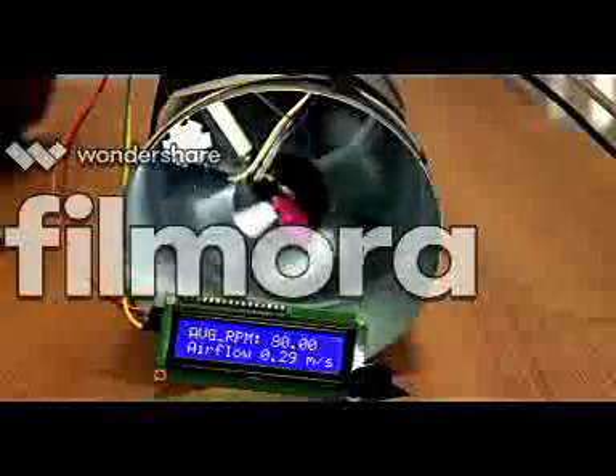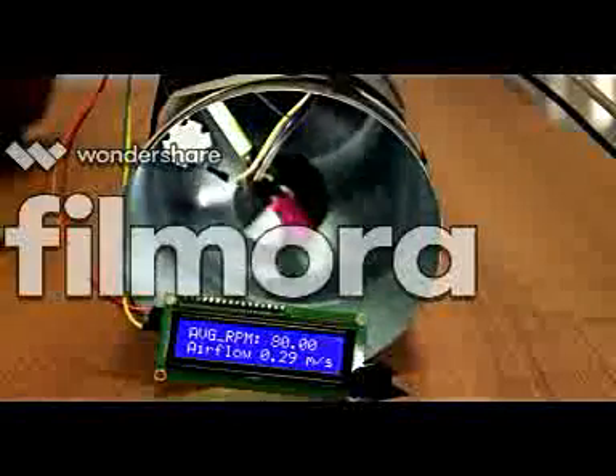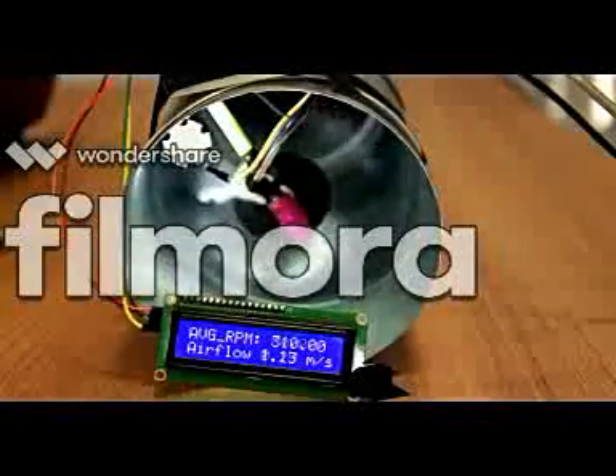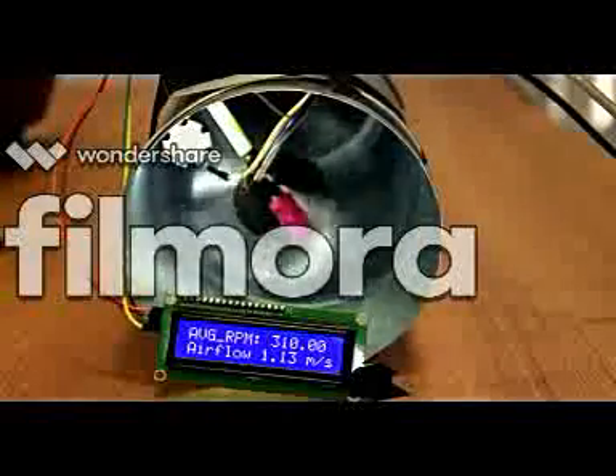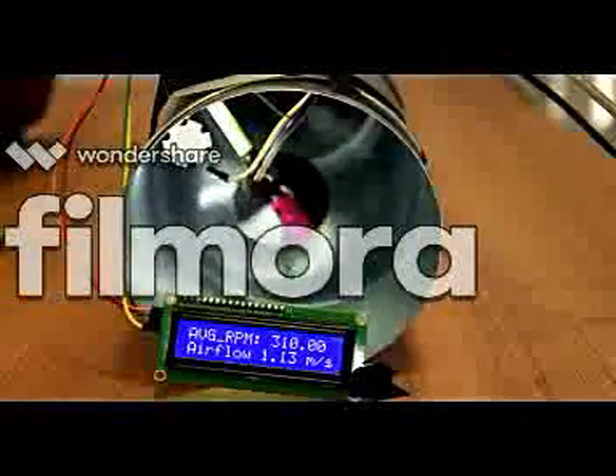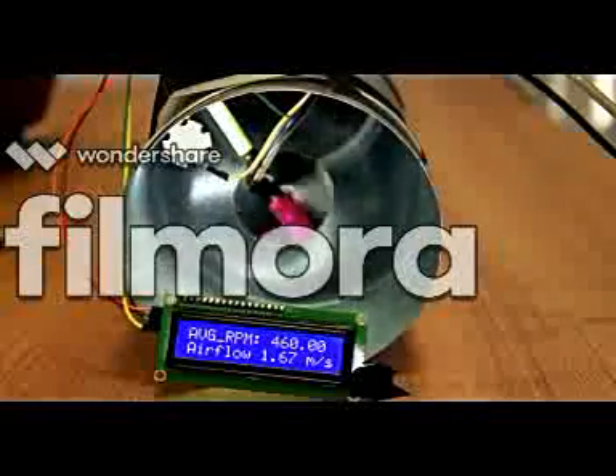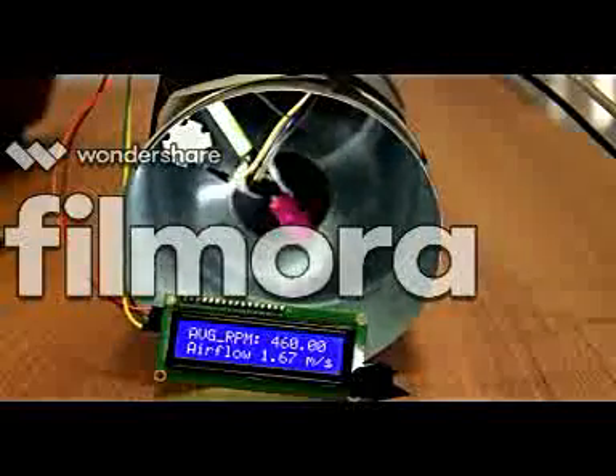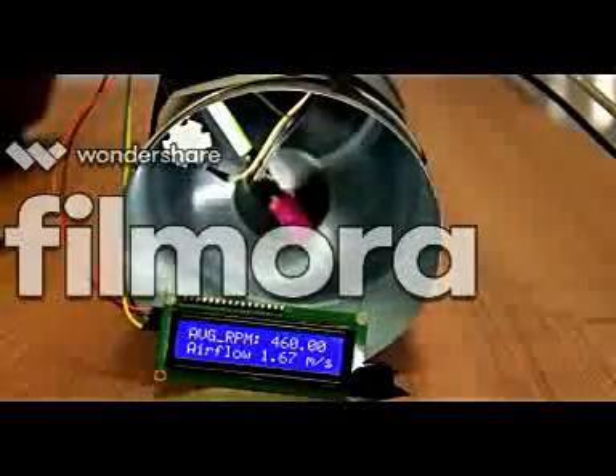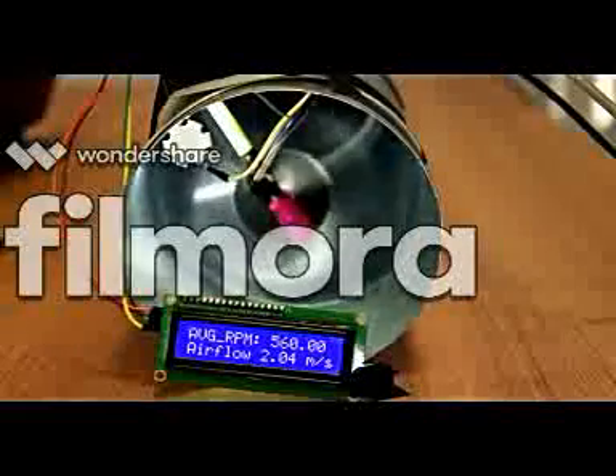The goal of this video is only to show the general principle underlying mechanical fan anemometers. Keep in mind that the device that I have built, despite the fact that it's pretty precise, is not very practical because it is extremely loud, causes huge turbulence inside the duct, is prone to mechanical malfunction, and dust gathering will lower the efficiency of the optical sensor.